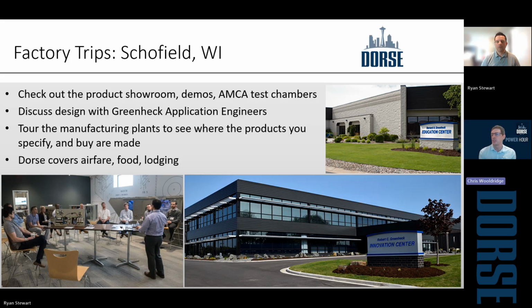With demand control ventilation, does the airflow at the external plenum need to vary with the exhaust? It does. Yeah. They'll modulate together to maintain that balance for both exhaust and supply. That's all part of the configuration and the logic of the control panel. It's a kind of a wonderful system Greenheck has. And again, when Ryan selects the equipment for this, we'll have a VFD or an EC motor on the makeup air, and then typically a VFD or an EC motor on that exhaust fan, and the logic of the controller will just track each other as necessary, and it's a nice system.